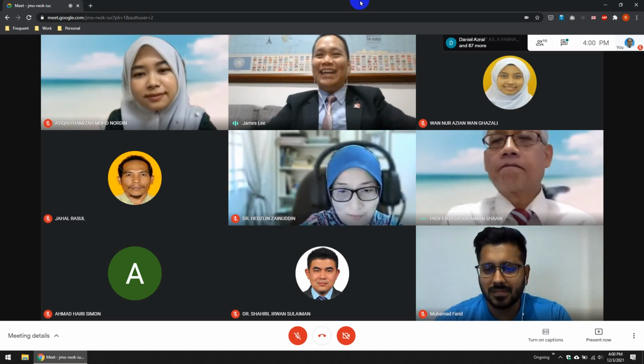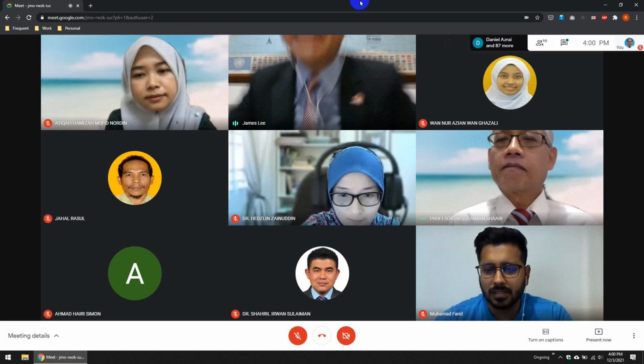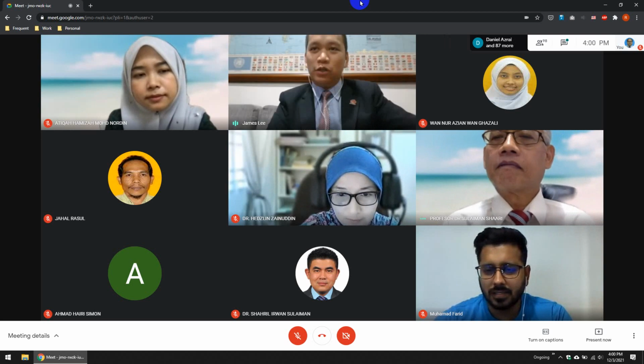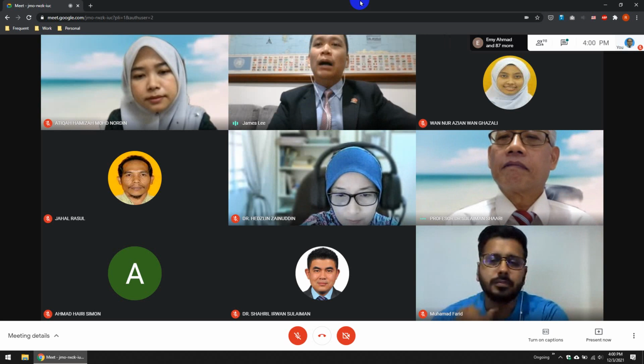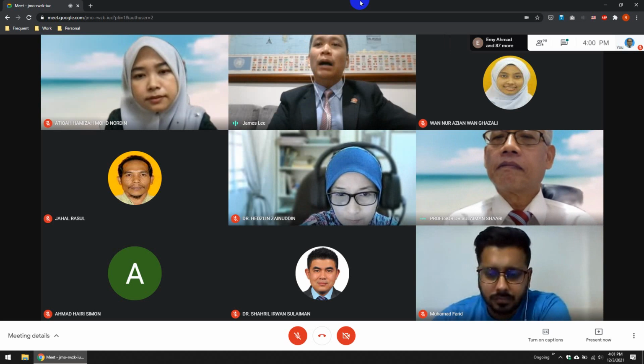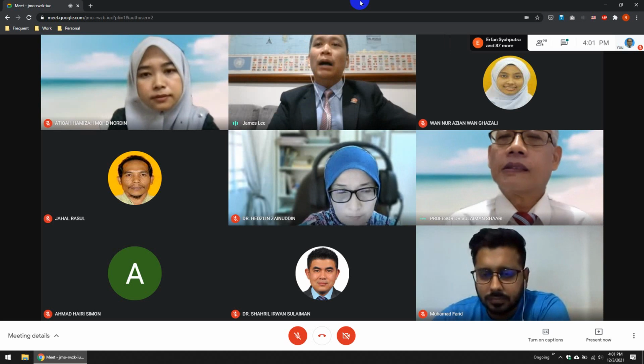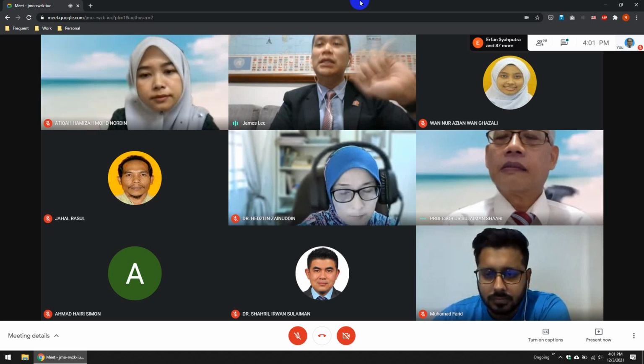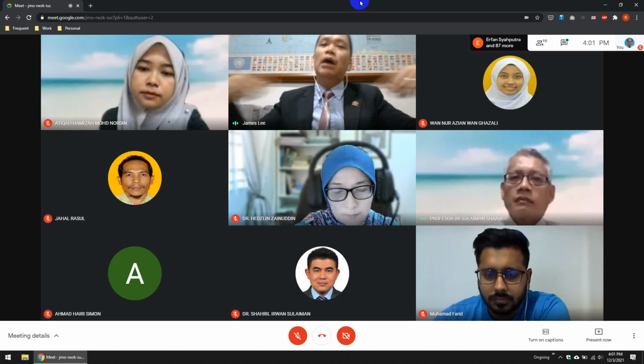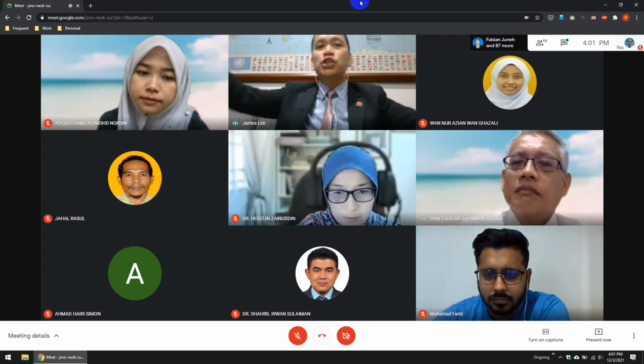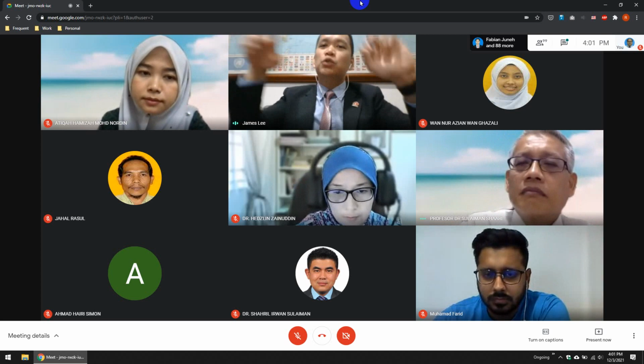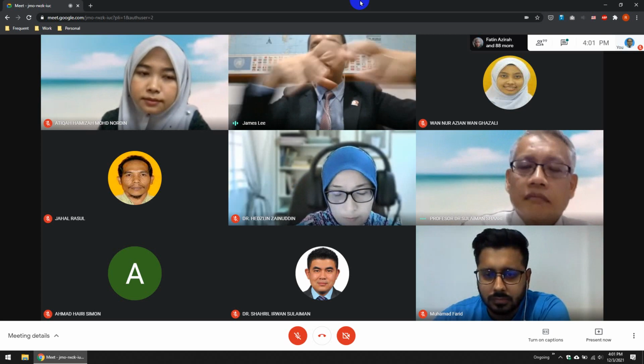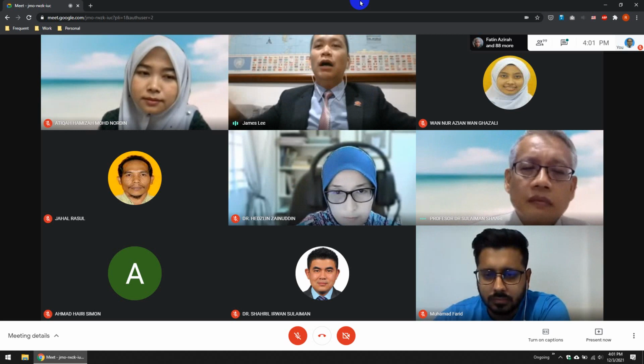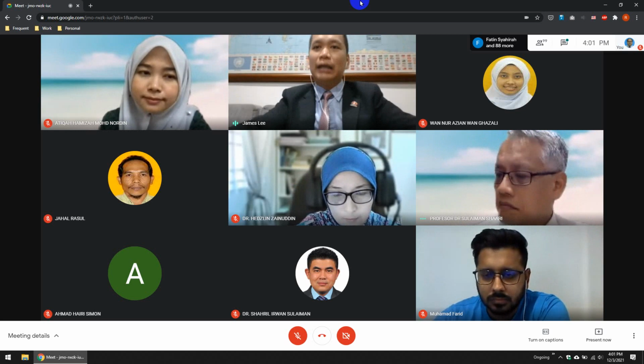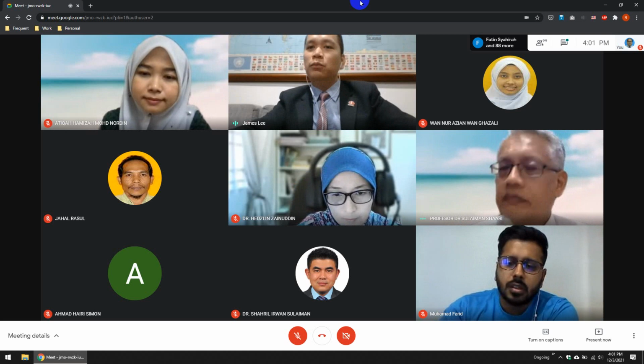On NEM 3.0 and owner self-consumption, yes, we have zero export capability, but this is only at one point of interconnection. If you're referencing from one meter with multiple sites, we need a third party, almost like a power plant controller, to negotiate between the one meter and multiple feed-in points. We've done a few projects, and I can share more information later.